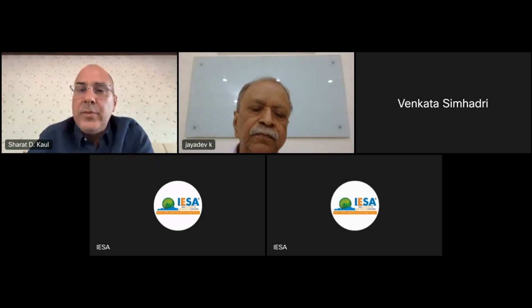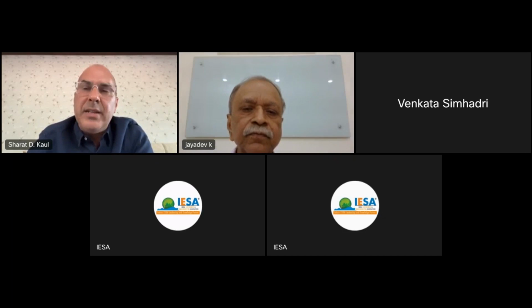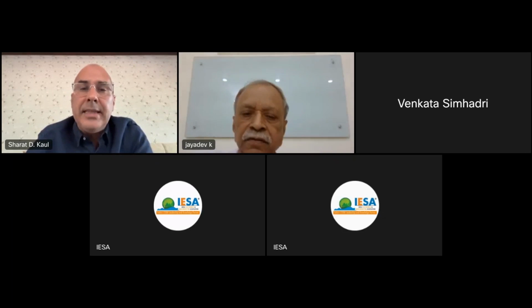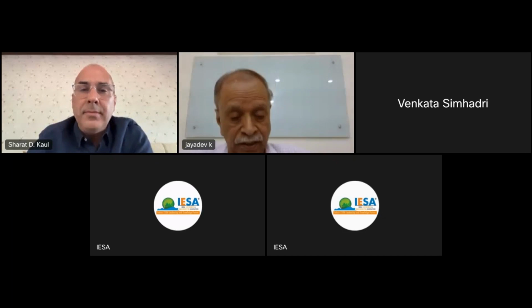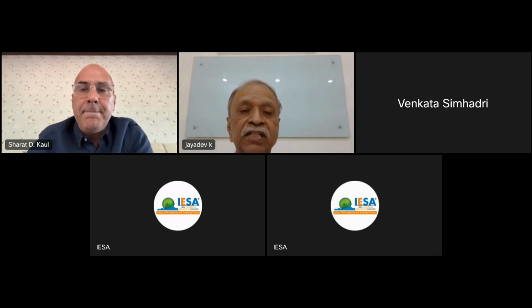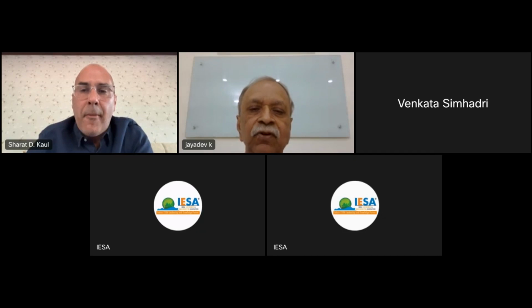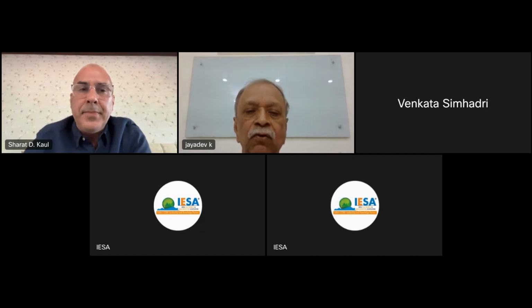Question from Shubhi Tandon. What equipment is required to validate a clean room for semiconductors? How do you validate the clean room? First, we have to check the velocity of the air flowing. The meters will be there to check the velocity. Based on the velocity, you can calculate Q equals V times A. When you know the velocity and the area of the filter, you can calculate the quantity of air coming.